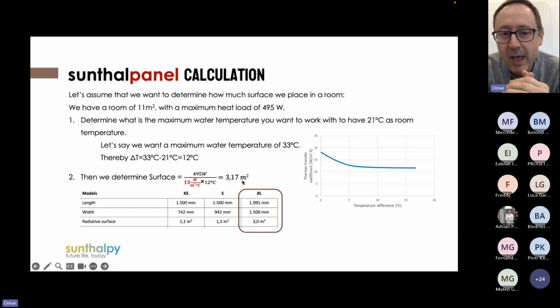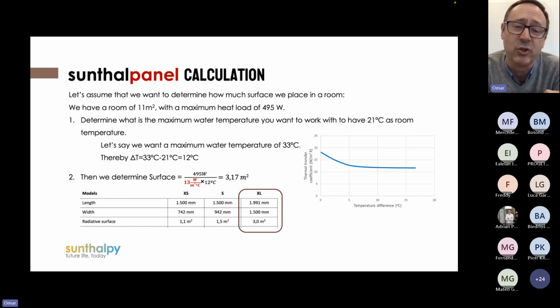Then what we get is 3.2 square meters. So basically we have three sizes for the Sunthalpanel. The biggest one is already 3 meters. In this case, there's no problem. We would go for an XL, which would guarantee that it will not operate above 33 Celsius to provide the heating. With the cooling, the ratio is the same, 13 watts. The only thing is you will not be able to work below dew point. That's your limitation. You won't have the possibility to work with 12 Celsius. Usually you can work with a temperature differential of 5, 6, 7, 8 Celsius maximum on cooling, but it's providing a superb cooling. It's like being in a cave. And if someone is interested in cooling, we can discuss further another day.